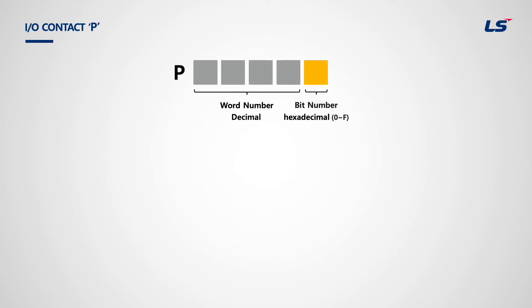Let's look at input-output contact P. Five digits are used to express P memory: the first four are for word and the last one is for bit. What's important is that the digits of memory are different depending on the product. Users need to be aware that the last digit shown in hexadecimal is bit. The other digits are word, expressed in decimal, while the bit is in hexadecimal.